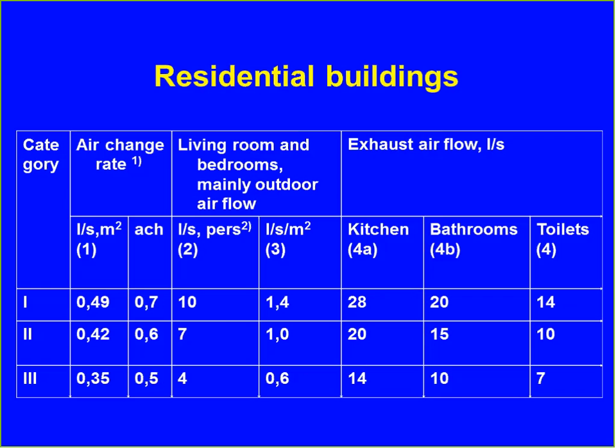For the residential buildings, I'm showing here the table which is in the existing standards. This is undergoing a lot of discussion at the moment. We will probably have some values for required exhaust from wet rooms. We will have some requirements based on total air change rate, but we're also discussing having something similar for non-residential based on people and the building.